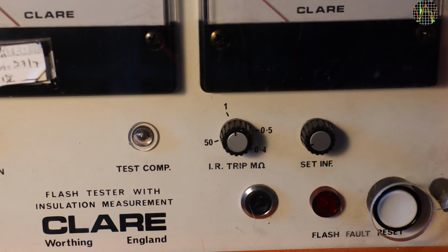The controls on the right are a light test complete, a control to set IR trip megohm. I suspect that IR stands for insulation resistance. I guess that if the value is set to 50, any measured insulation resistance lower than that will cause a trip, in other words, a fail. The round knob at the most right is set inf. I guess this knob is to set the instrument to show inf if there is nothing connected to the output, as kind of a calibration.